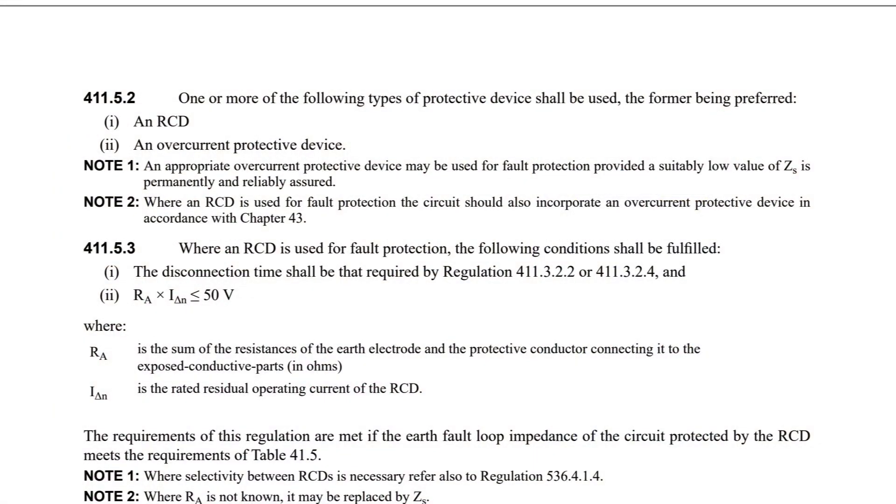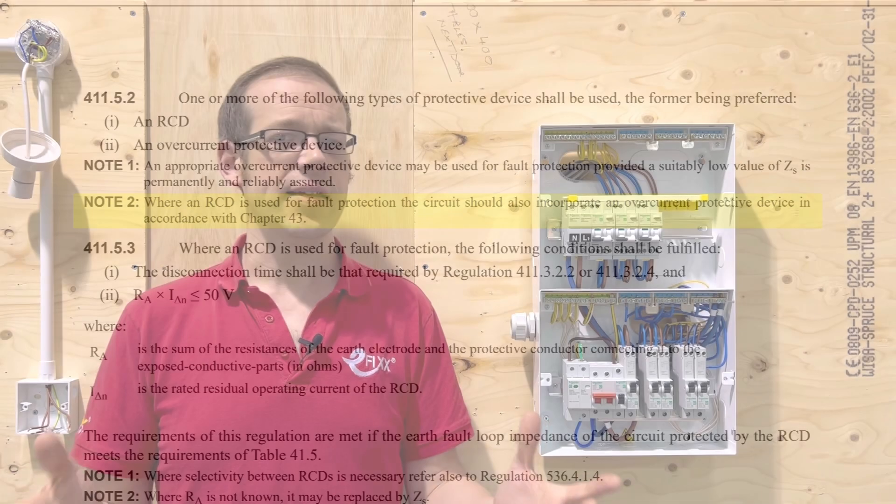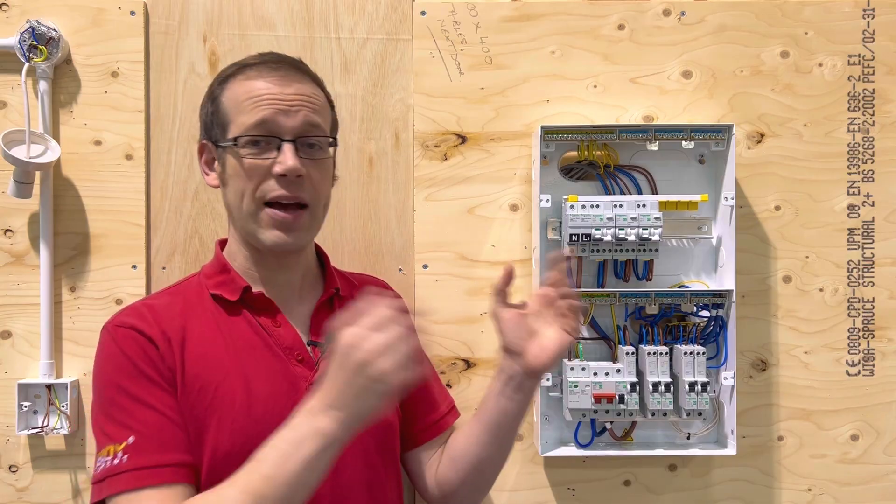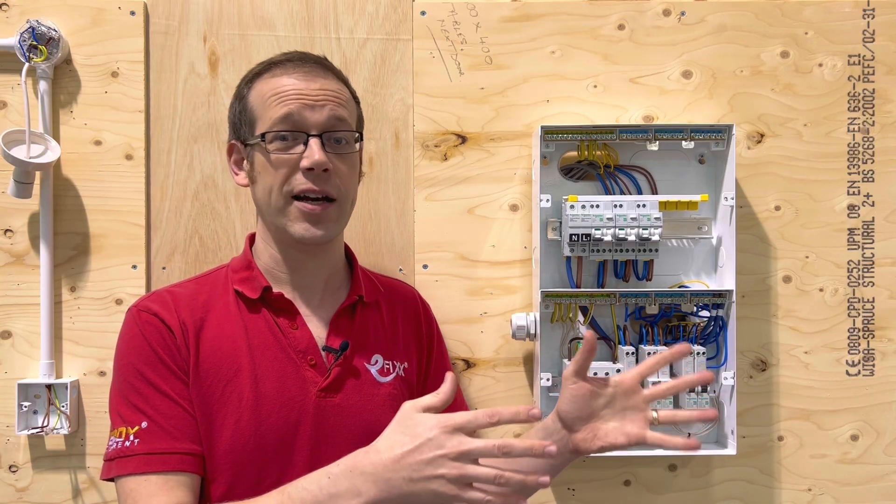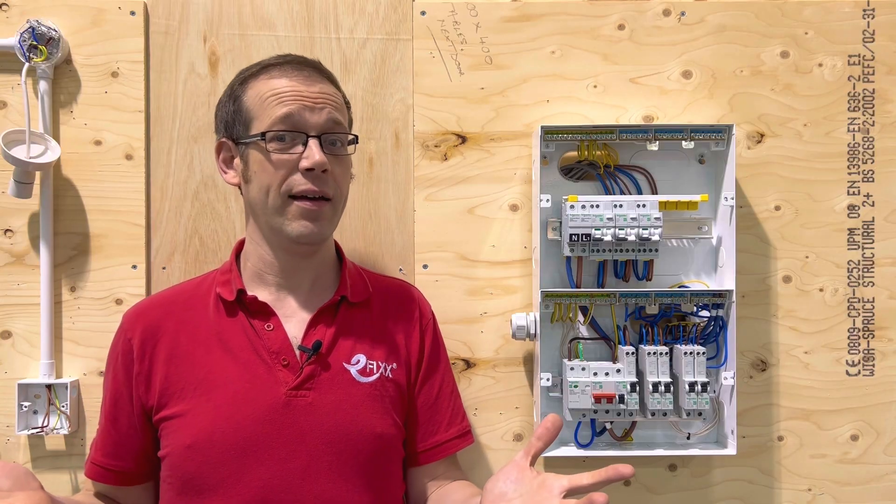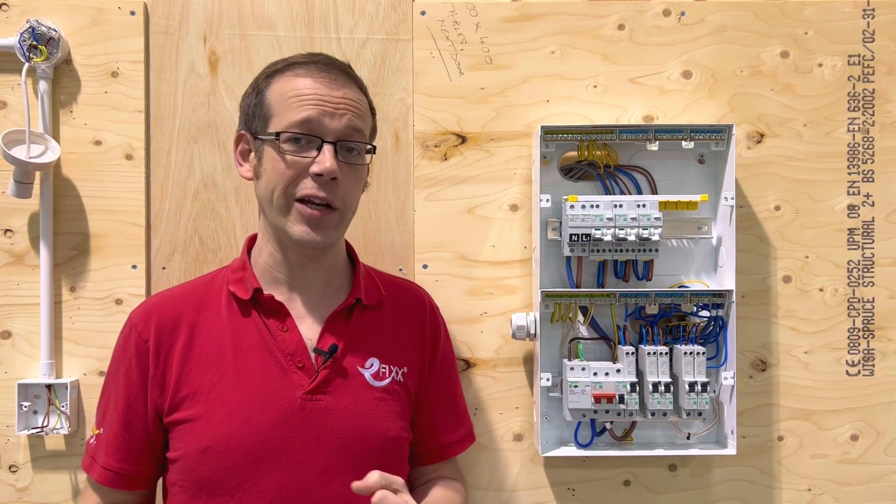Note 2 is also worth a look. That says where an RCD is used for fault protection the circuit should also incorporate an overcurrent protective device in accordance with chapter 43. So that makes sense as an RCD by itself won't monitor for overcurrent. It could have thousands of amps flowing through the line conductor and as long as it's exactly the same amount flowing back down the neutral it won't care and it won't trip even if the building is burning down around it.